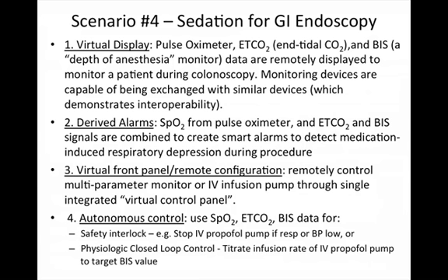The interoperability aspect of this scenario is the notion that the devices are capable of being exchanged as needed. So perhaps we want to swap one pulse oximeter with a certain set of capabilities for a different pulse oximeter. And when we do that, because the devices are interoperable, we will continue to have the data displayed on that virtual display across the procedure room.